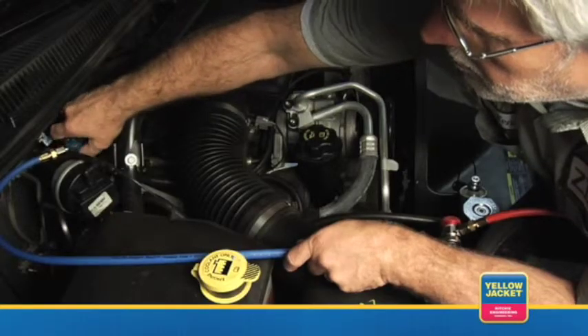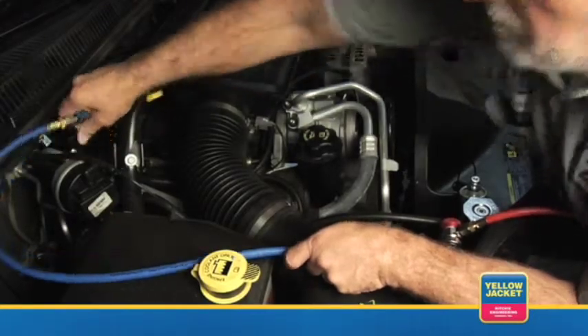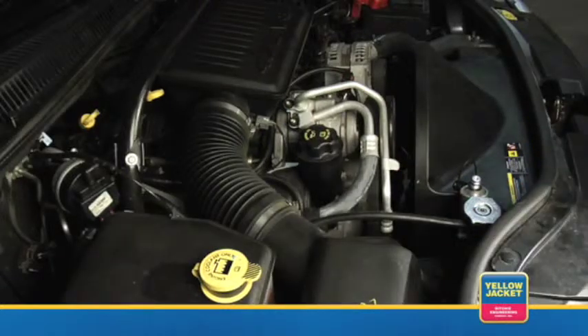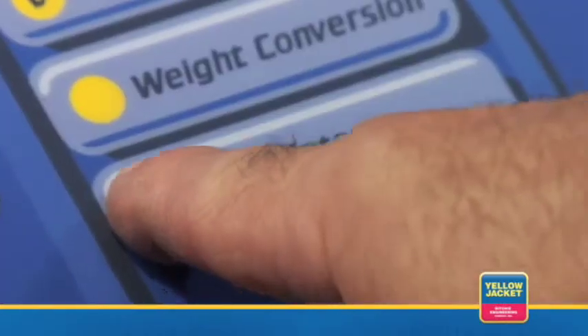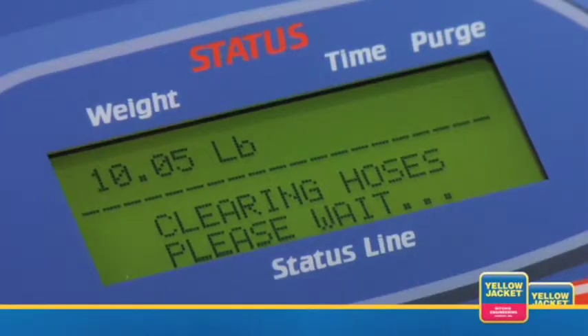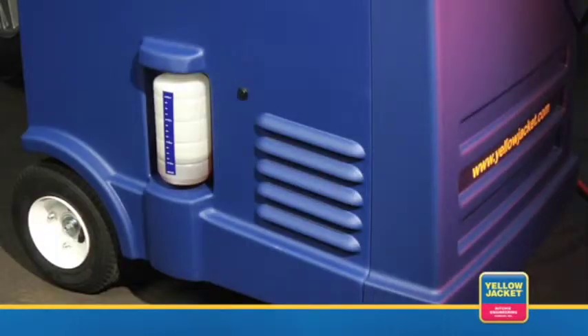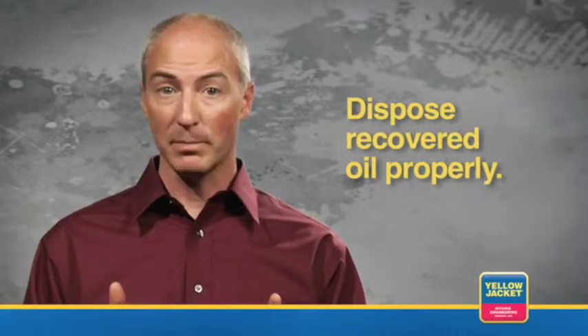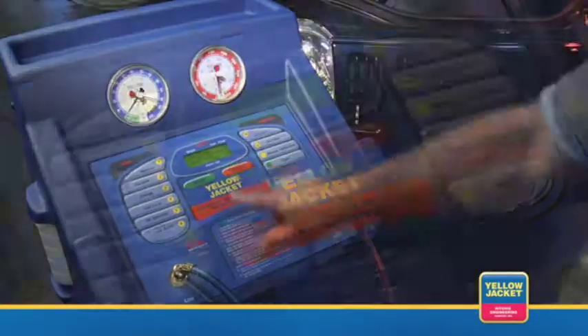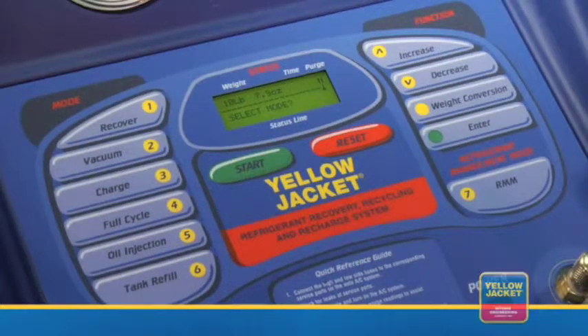Shut the service valves and disconnect the high and low side auto service hoses from the automobile. Press Enter one more time and the LCD will read Clearing Hoses. Lastly, measure the oil in the oil drain bottle, dispose of the recovered oil using proper procedures, and press Reset to return to the select mode status.